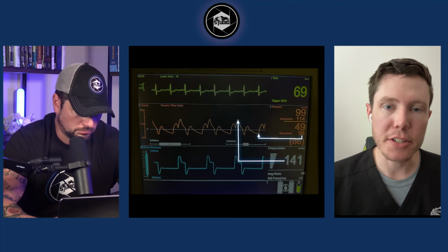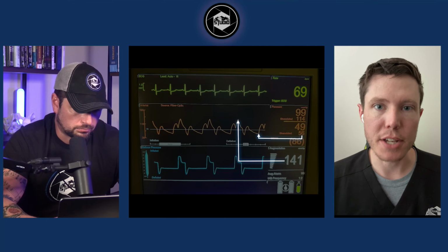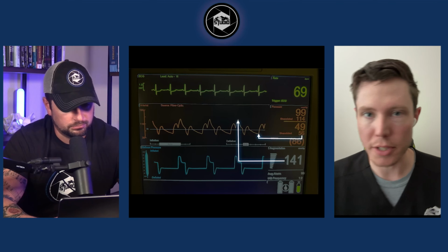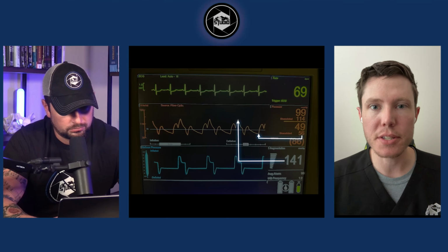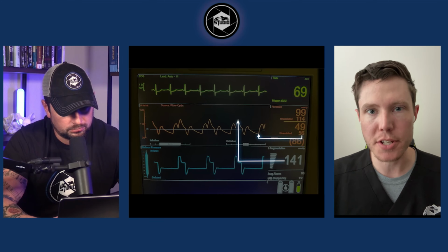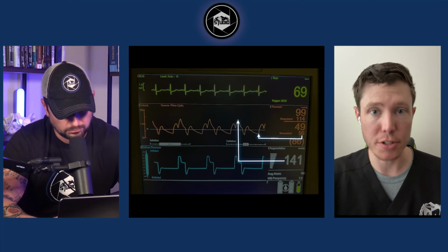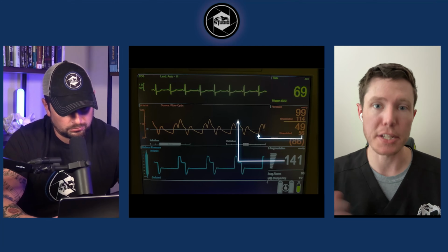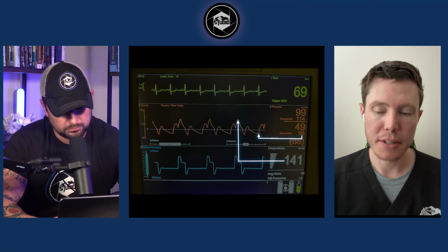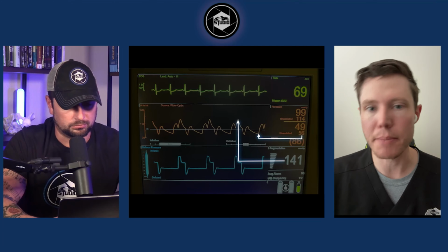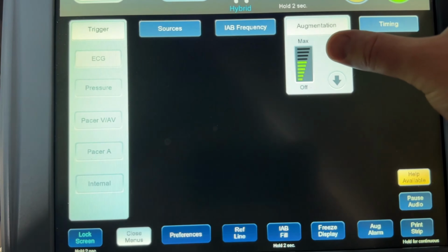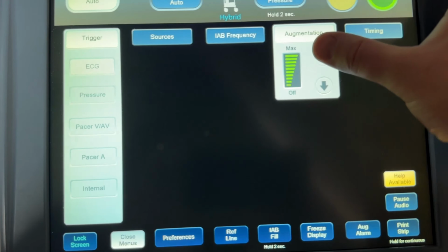Now you can decrease the augmentation to say like 75%, and then a 40 cc balloon would only get filled with 30 cc's of air or helium. So by doing that, you decrease the pressure inside of the balloon, which means you're pushing less pressure into the aorta, which means you're going to get less pressure at the assisted diastole. Does that make sense? The way I described that? Yeah, that's what I was going to ask. So 100% augmentation means you are filling up that entire balloon to its 40, 50 cc capability.